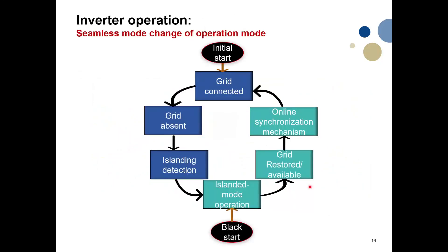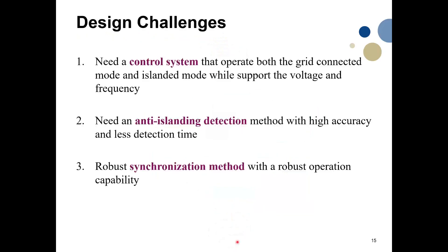We can now see the complete seamless operation sequence for the inverter-based microgrid: starting with offline synchronization and grid-connected operation, then when the islanding detection technique detects grid absence, transitioning to islanded mode, and when the grid is restored, performing online synchronization to reconnect to the grid. This forms a complete cycle — a plug-and-play capability where the converter can supply power to local loads and also operate in grid-connected mode without being turned off.